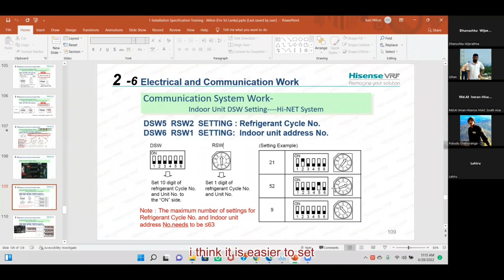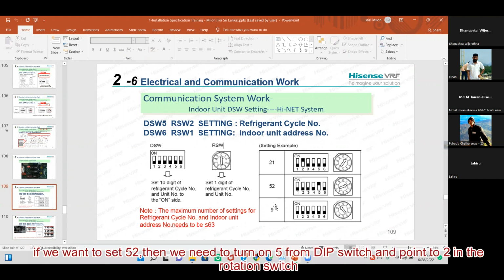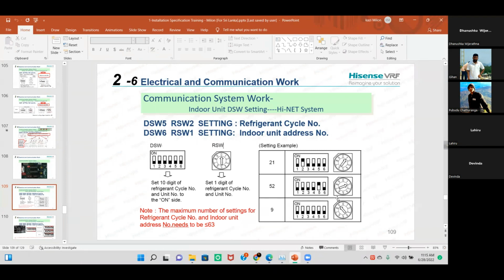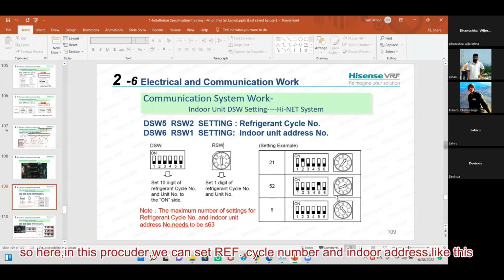I think it is easier to set. If we want to set 52, then we need to turn on 5 on the DIP switch and turn the rotary switch to 2. So in this procedure, we can set the refrigerant cycle number and indoor unit address settings.